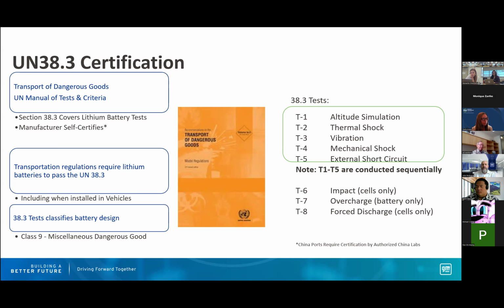Then there are additional tests, T6, T7, T8, for impact of cells, where they have to go through a certain impact and demonstrate they won't rupture or have a thermal event — overcharge for the battery only, and then forced discharge, because when you overcharge or force discharge a battery is when it can become unstable. So you have to prove your design type will pass all those different criteria.